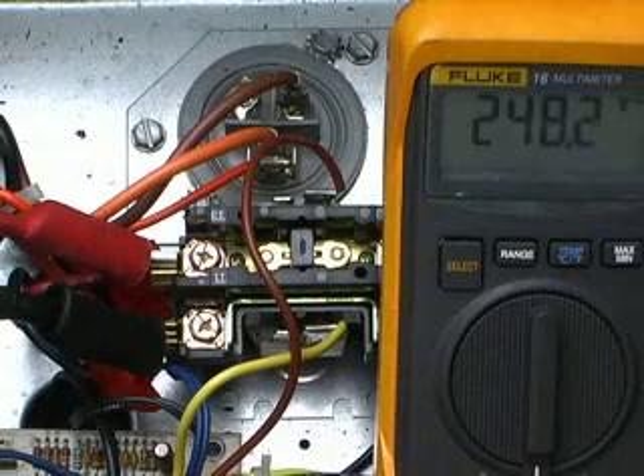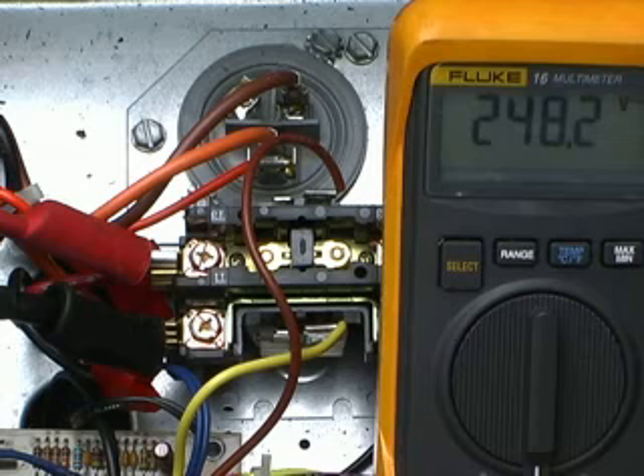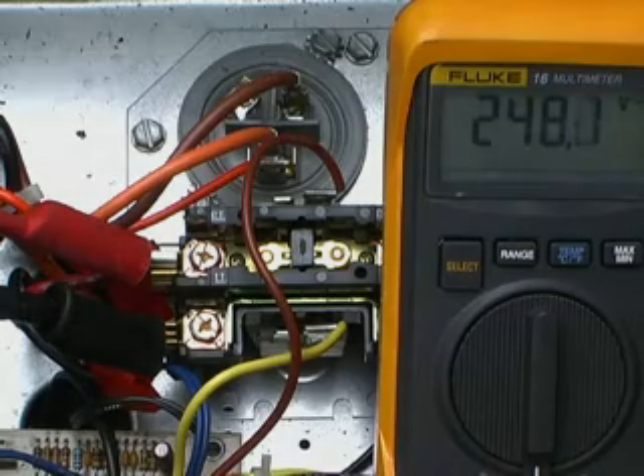Of course, now the other situation: you have 240 volts coming out of the contactor and still nothing's running. At this point you need to suspect the condenser motor and/or the dual run capacitor.